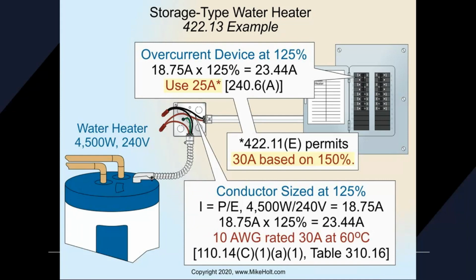Here's a good example of where we're at with that. Overcurrent device at 125%. So if I said 18.75 amps is what the water heater said, I end up using a 25 amp breaker. But if I was unaware of the 125% rule, I would just answer the question as a 20 amp. See how you can get caught in that? There's a further exception, or another code. 422.11(E) permits you to go all the way up to 30 amps based on 150%. Okay? Purely resistive load water heater allowed to go up to 150% in some cases. Take a look at 422.11(E).